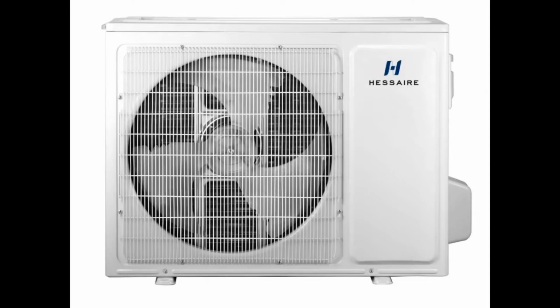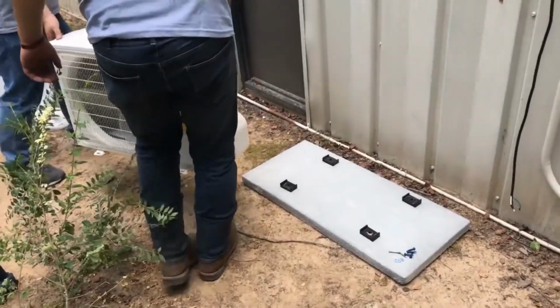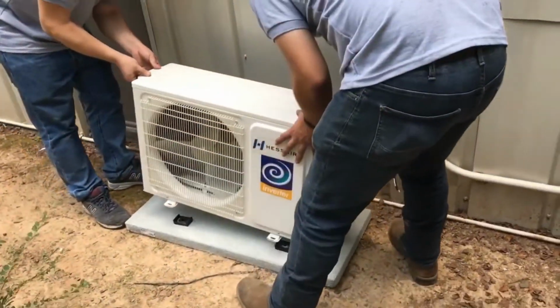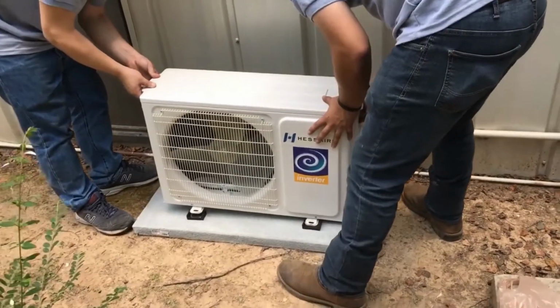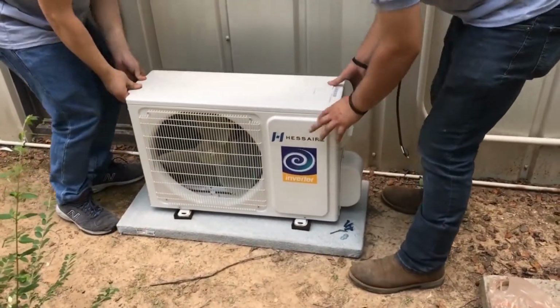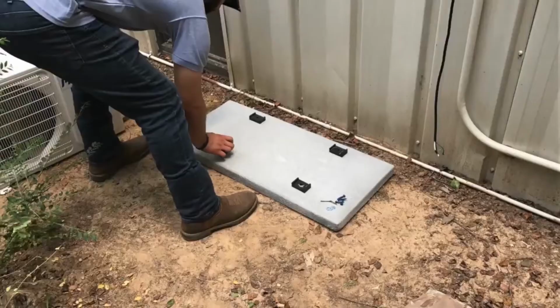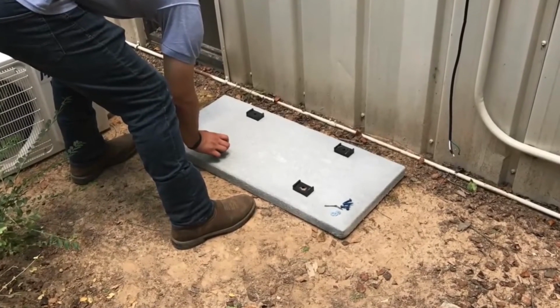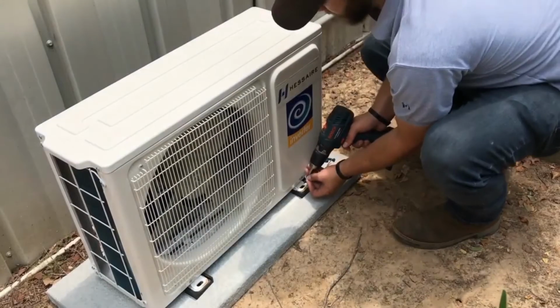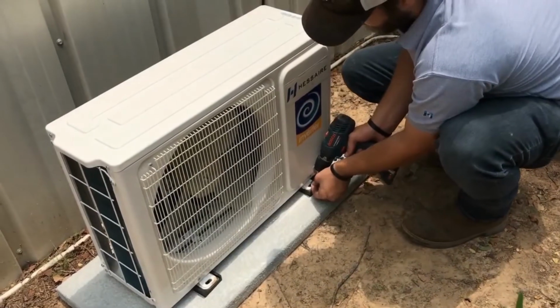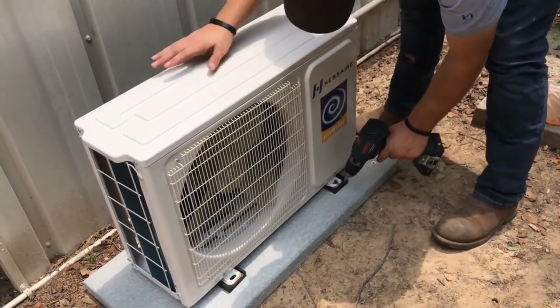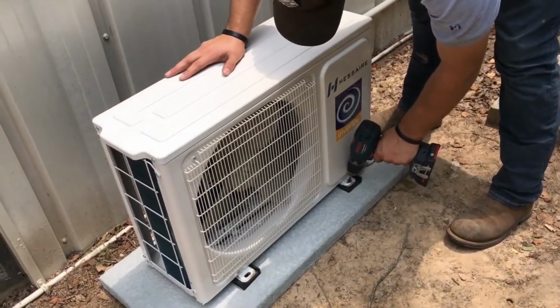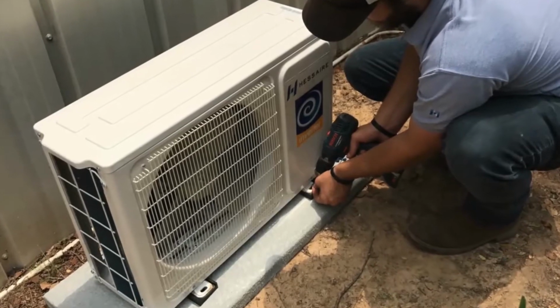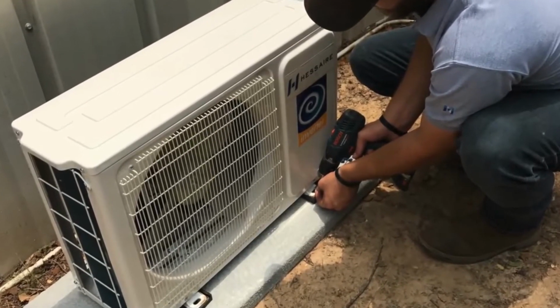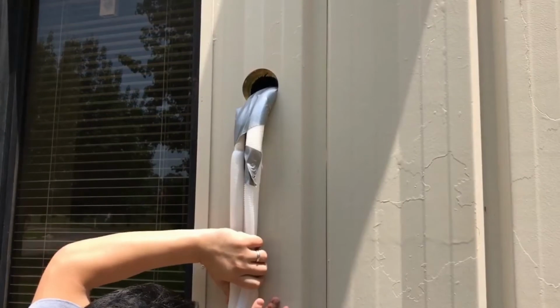Choose the outdoor unit's location based on your home structure, local codes, and convenience of installation. You can place the unit on a pad, mount it on an exterior wall using brackets, or place it on a rooftop. We're using a pad, the simplest and easiest method. The outside unit should be securely mounted with bolts through the footholes before making any connections. With the condenser securely mounted, you can make your outside connections.